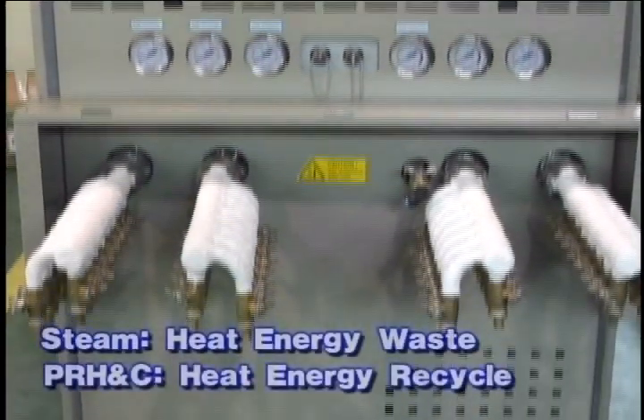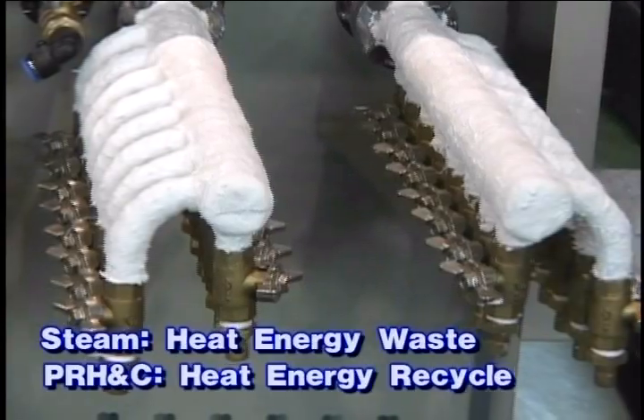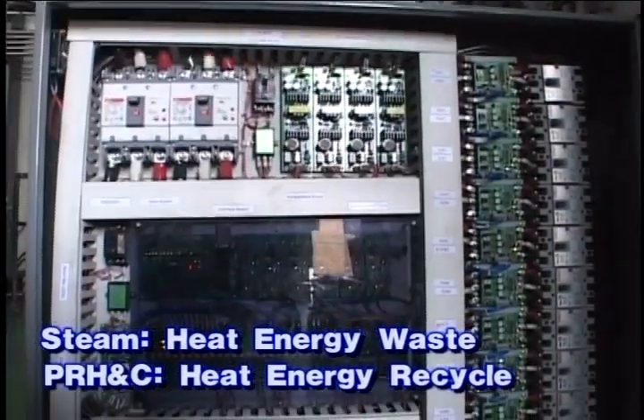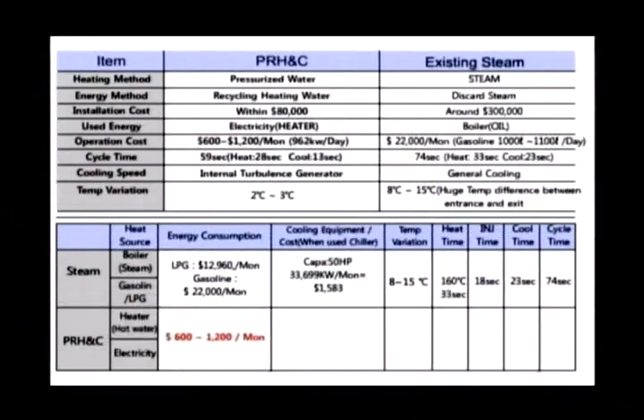This shows excellent energy consumption rate compared to that of steam boiler or pneumatic jet steam method. In case of steam, once thermal energy is jetted, it is impossible to draw it back. The pressurized water moving in the closed circuit does not send heat out. There is no energy loss because the hot water returning after heating the mold is able to be recycled.